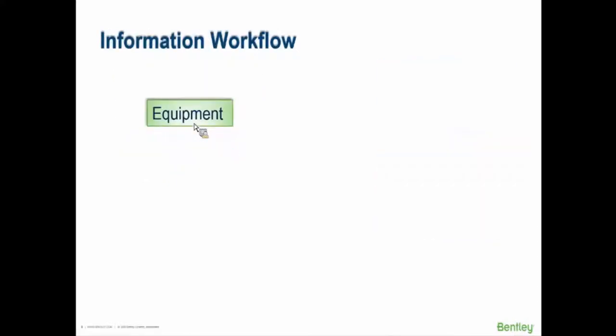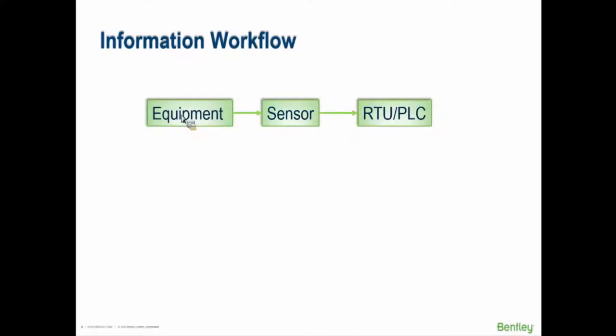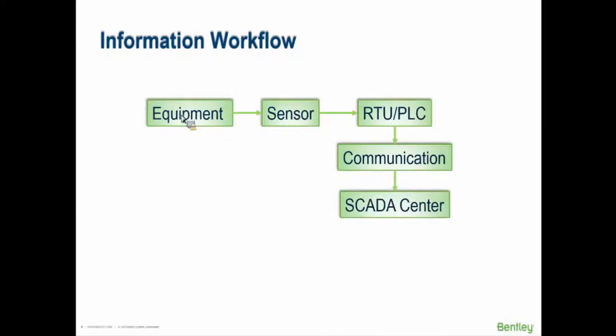Here's an overview of how data flows. You have some piece of equipment out there — a pressure gauge, a flow meter, a tank level indicator — with a sensor. That sensor goes to an RTU where it does analog-to-digital conversion, stores it, and sends the signal back to the main control room and the OPC server. That is then displayed in the HMI — the human machine interface — which is what you see on the screen connecting the server data with the operator. The operator sees the tank level, which pumps are running, and the flow rate at a flow meter.